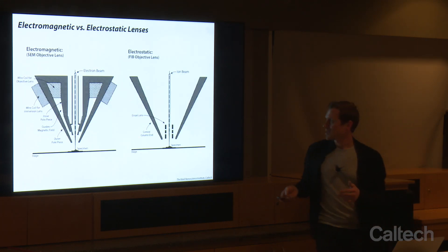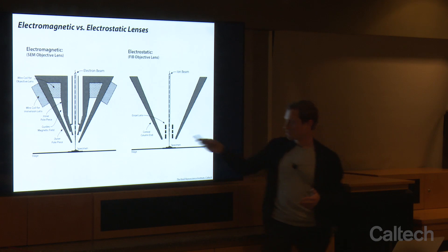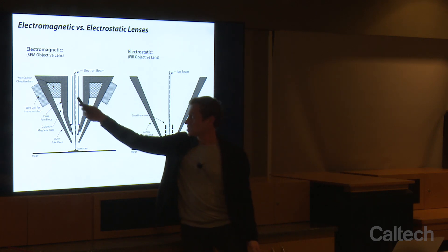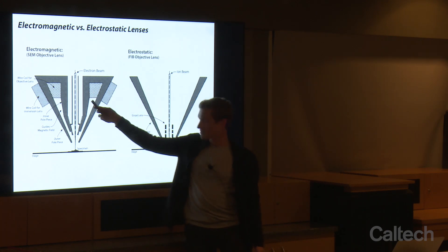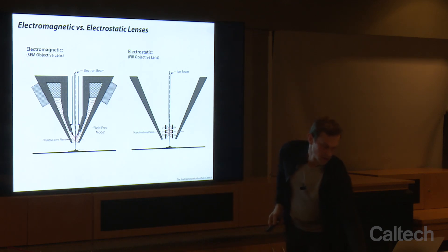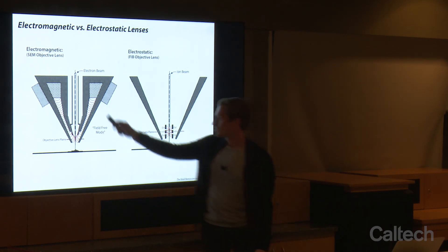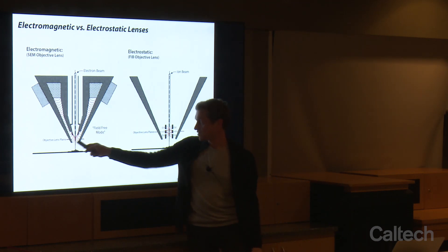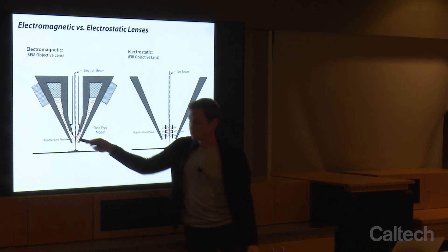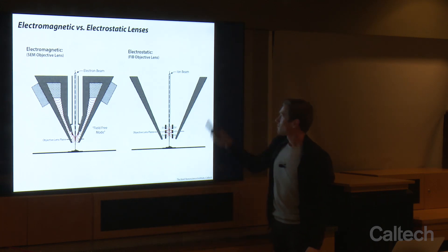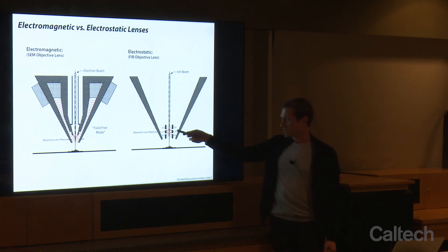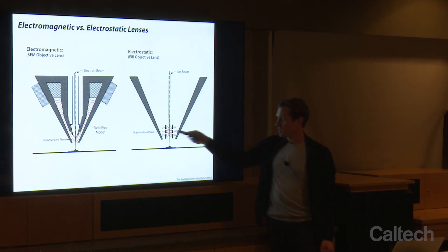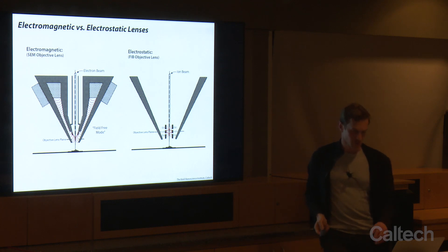Here's the bottom of our column. The objective lens in an SEM is that wire coil at the bottom — when turned on, the magnetic field leaks out. For a gallium-focused ion beam, we put one of these Einzel lenses at the bottom of the column and that becomes our objective lens plane.